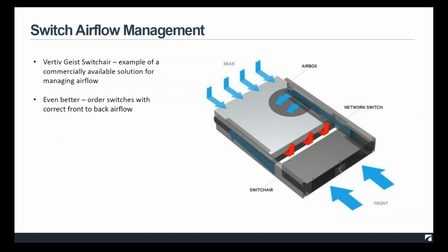So switch airflow management. Those top of rack switches and other switches are notorious in not doing the traditional front to back airflow. So in your ideal case, and as is the case with most servers, they draw in air in the front and they discharge it in the back. In many cases, switches don't do that. Sometimes they will go side to side. Sometimes they'll pull in the hot air from the back, and discharge the even hotter air into the front. So there are commercially available solutions for that sort of thing. The first solution is if you can talk with your network engineer and have them order a switch that draws in the air from the cold aisle and discharges it into the hot aisle. That's going to be the simplest solution. But there are some commercially available solutions that will help with this particular issue. Next slide, please.